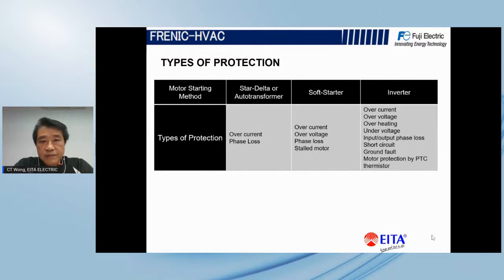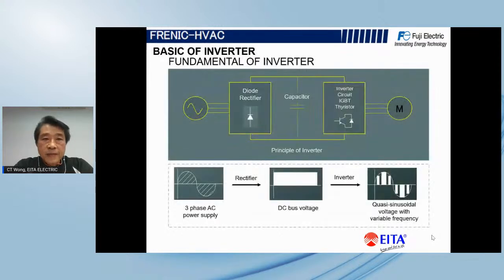Type of protection: you can see over here that direct online, autotransformer and star delta are the same. Basically they cover overcurrent or phase loss. Soft starters have slightly more. For the inverter, at this moment the protection is still the best: besides overcurrent, there is over voltage, overheating, and also short circuit on the inverter output, ground fault on the inverter output, and you can also connect the PTC to the inverters.